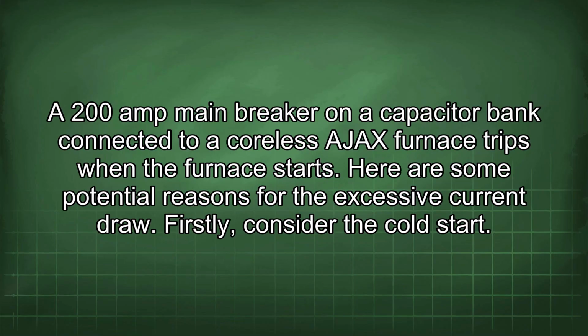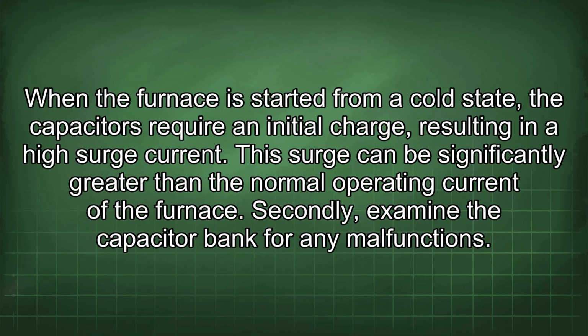A 200-amp main breaker on a capacitor bank connected to a coreless AJAX furnace trips when the furnace starts. Here are some potential reasons for the excessive current draw. Firstly, consider the cold start. When the furnace is started from a cold state, the capacitors require an initial charge, resulting in a high surge current. This surge can be significantly greater than the normal operating current of the furnace.